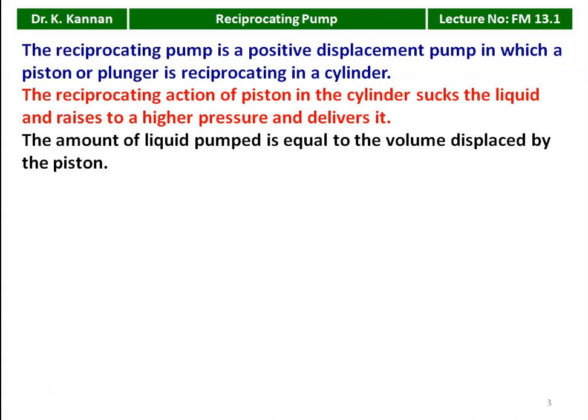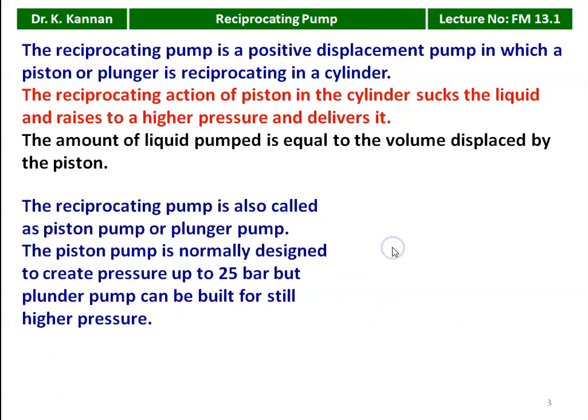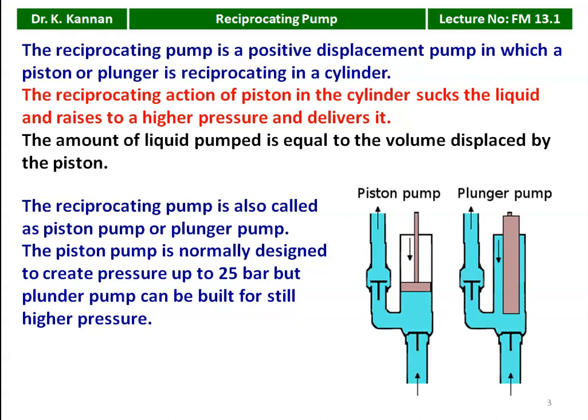The reciprocating action of the piston in the cylinder sucks the liquid, raises it to higher pressure, and delivers it — similar to an internal combustion engine where the piston reciprocates inside the cylinder. There will be a suction stroke and a delivery stroke. During the suction stroke, the liquid is drawn into the cylinder; during the delivery stroke, the piston pushes the liquid at higher pressure and delivers it. The amount of liquid pumped equals the volume displaced by the piston. The reciprocating pump is also called a piston pump or plunger pump. The piston pump is designed for pressures up to 25 bar, but the plunger pump can be built for still higher pressure.